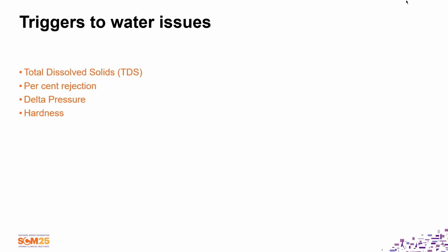So if you're looking at your system and those people that are monitoring it see an upward trend, it needs to be reported. It cannot be reported when it's alarming. And the reason why you monitor for trend is that you take action before it actually becomes a problem. And that's the same thing with doing cultures, and I'll cover that later on. So TDS, that. Also, percent rejection. Percent rejection needs to be trended, but percent rejection is the proportion between incoming water and the product water. So you take that relationship and that's your percent rejection. Some parts of the country's water is so good that the incoming water is pure enough so that it doesn't give you a 99 percent rejection in relation to your product water. So if you're in those kind of facilities, you don't have to do anything.